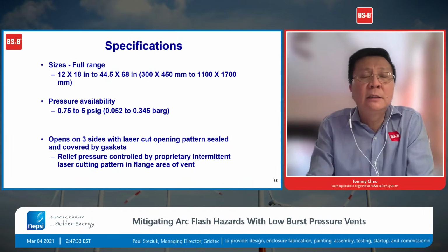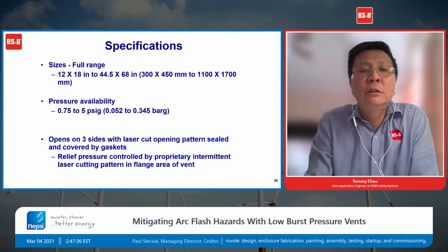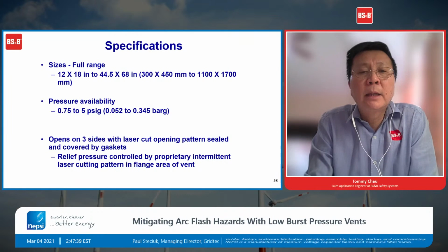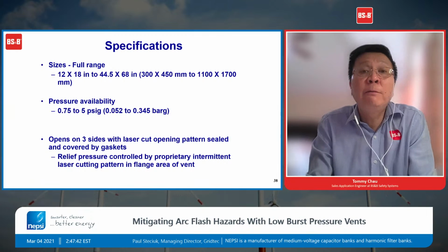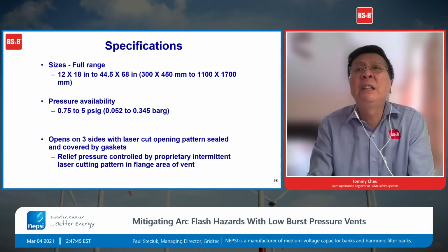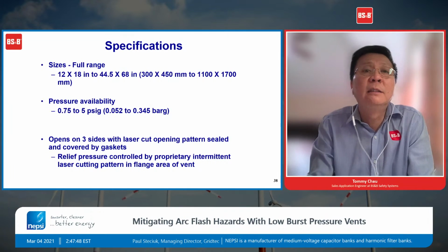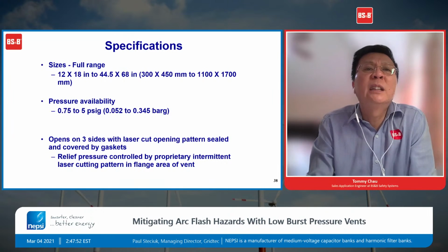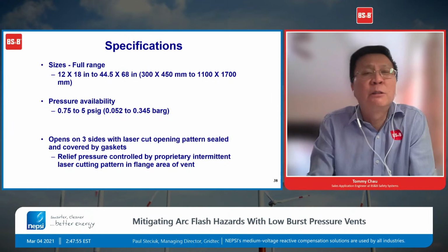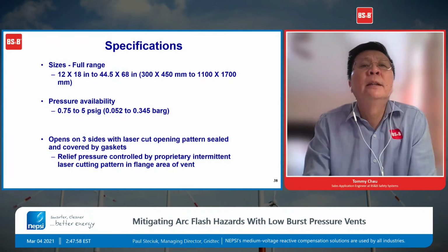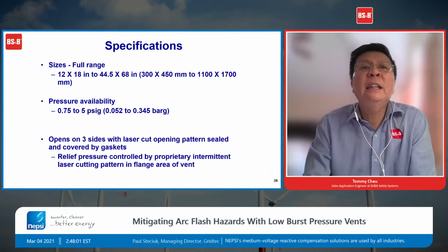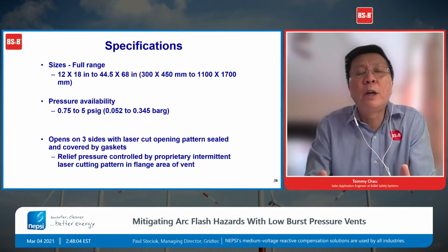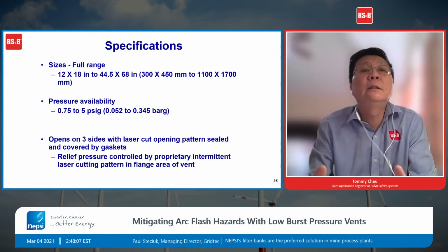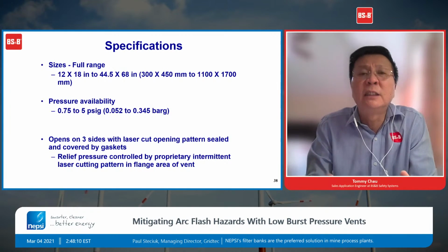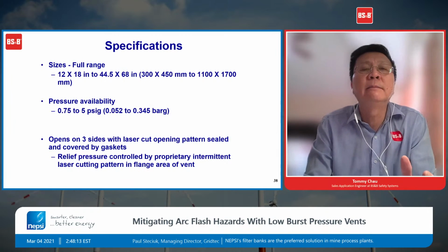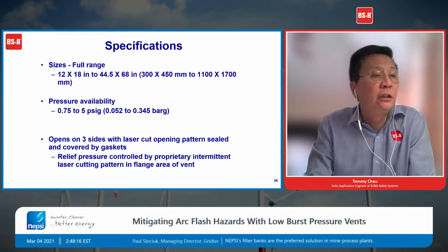Again, the sizes I think we mentioned earlier are 12 by 18 inch all the way to 44.5 by 68. On a 44.5 by 68 inch panel, you have a total net relief area of approximately 21 square feet. Burst pressure, again, is 0.75 to 5 psi. We get down to half a psi if we need to on a big panel. It is laser cut in a way that the panel is a non-fragmenting design, so it won't come off when it activates. We have an uncut area that acts like a hinge on the explosion vent.